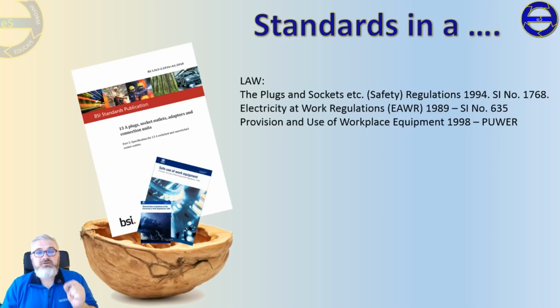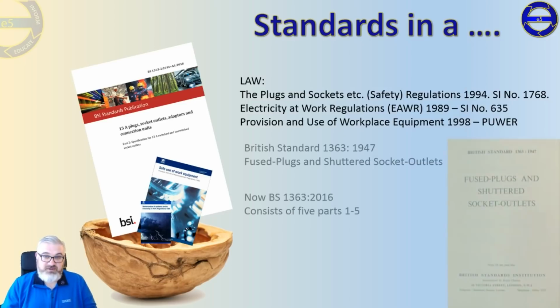Remember, USB socket outlets are part of the fixed installation and covered by BS 7671. However, the installation is also covered by the Electricity at Work Regulations, the Plugs and Sockets Regulations, and the Provision and Use of Workplace Equipment Regulations. So if you're in a workplace with a desk that has socket outlets on it, there's a requirement for maintenance, inspection, and compliant equipment provided by the employer to the employee. There's lots of legislation around that.